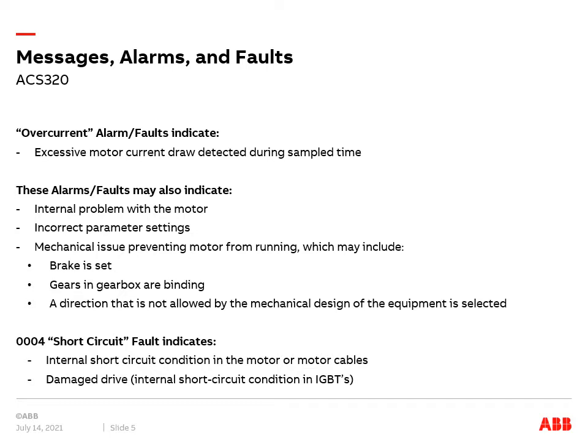Causes of overcurrent can be problems with the motor, bad parameters especially for the motor, and mechanical problems.